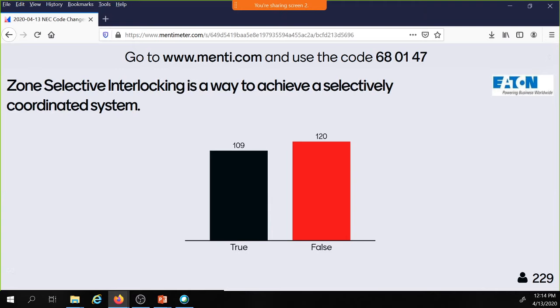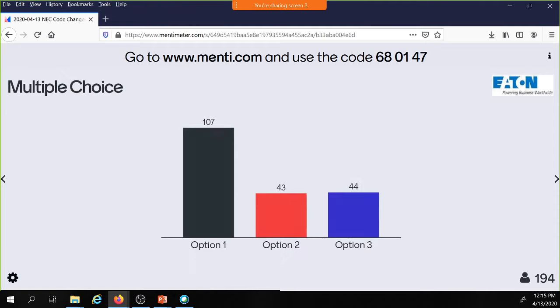We've sold that for years. We never sold it to meet selective coordination requirements. We sold it to provide equipment protection and reduce the arc flash and incident energy should an event occur on the bus inside of that equipment. So this is split. One of these days, everybody's going to be in the false column, and I'm going to feel very good about myself, and I'll never have to give this question again. I'm looking forward to that day.